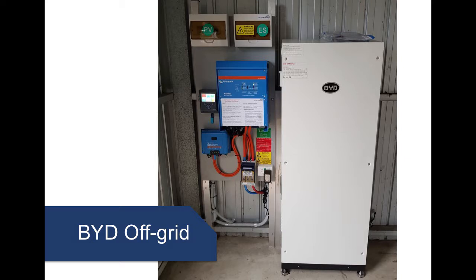So if you wanted to run a heat pump hot water system and you've got a pool, you've got pool pumps, high energy requirements during the day that exceed the battery inverter, there's a bit more power available because you can layer that over the top. That's one of the benefits of AC coupling.